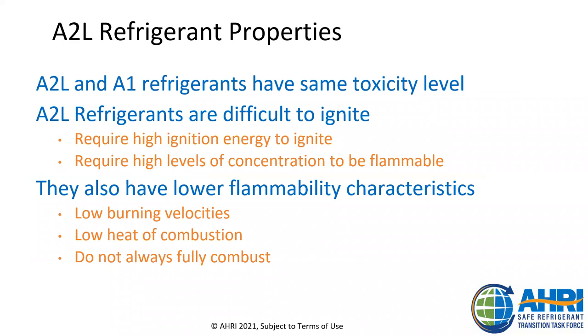A2L and A1 refrigerants have the same toxicity level, that's the A. A2L refrigerants, as I've been discussing, are very difficult to ignite. They require a high minimum ignition energy, or a very strong spark or a live flame, to ignite them. And they require higher levels of concentration to be leaked into a space to be flammable. They have lower flammability characteristics because they have a low or slow burning velocity. They have a low heat of combustion. And typically these refrigerants do not fully combust in a fire situation.